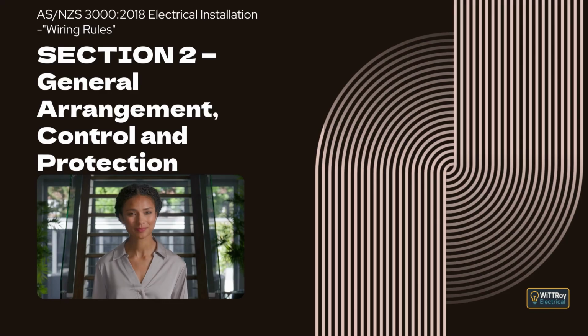Devices used for emergency switching must be clearly marked so people can recognize them instantly. Handles, levers, or push buttons must be permanently identified and must be colored red with a contrasting background. There is an exception. If a lanyard, chain, or rope is used for remote operation of an emergency stop device, such as above a conveyor, it does not need to be colored red. Clause 2.3.6, Shutting down for mechanical maintenance.